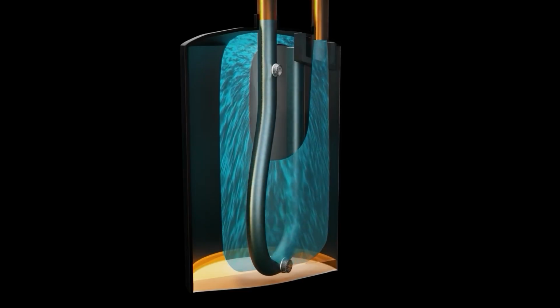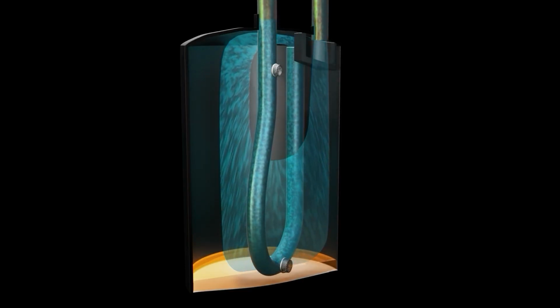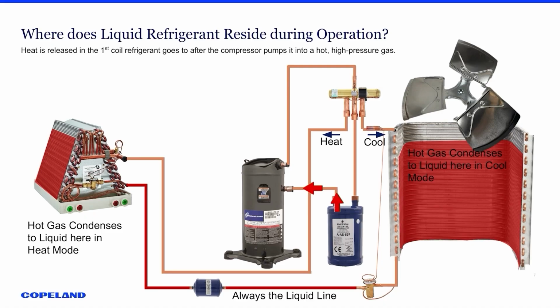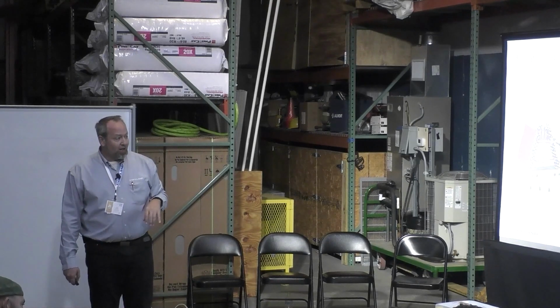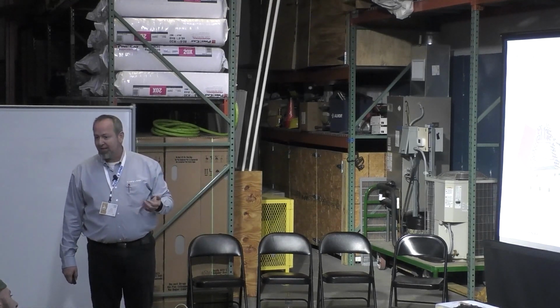And in the bottom, there are holes in it, small enough so that as oil comes back through to get back to the compressor, it starts filling up the bottom of this canister. Those holes allow that oil to go in at the bottom and to be drawn with the vapor, with the tube going almost to the top, all the liquid settling to the bottom of the accumulator, the vapors at the top. It's pulling the vapors off the top down past that oil seeping in those holes and carrying that oil to lubricate the compressor and get back to the compressor. So a couple of important pieces there.